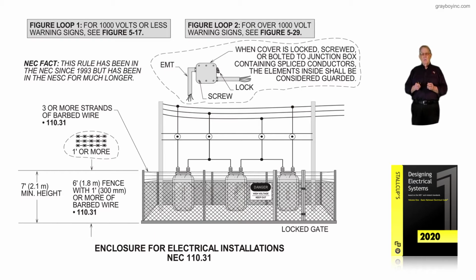And notice that label would have an orange color to it, telling you with a warning. And once you walked in, those high voltage terminations on that primary, if you could reach up and touch them, then you'd have to have a little fence around those, and that fence would have a gate with a label that was red, danger. Now, we know those warnings are recommended to us in Z535.4.